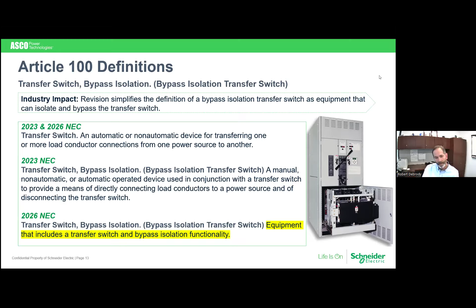So it's just a way to get around the permanent transfer switch in case there's a failure, or it's down for service or even for testing. NFPA 110 says that for emergency systems, you must test the transfer switch once a month, and you must test your generator once a month. So the easiest way to do that would be to bypass it and then test your transfer switch along with the generator. Hope that's all clear. I know I raced through that pretty quickly.